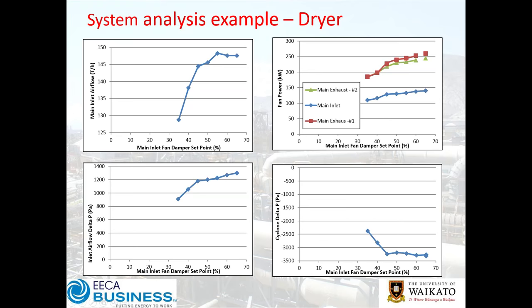To the right you've got the same inlet fan damper set point and the corresponding exhaust fans — two exhaust fans — and their power consumption. You'll notice that going from 65% down to 35% made quite a difference in flow rate, initially not a lot then it dropped off. This is a really good example of how system effects aren't uniform — they can change and shift, with system curves not necessarily being nice parabolas.